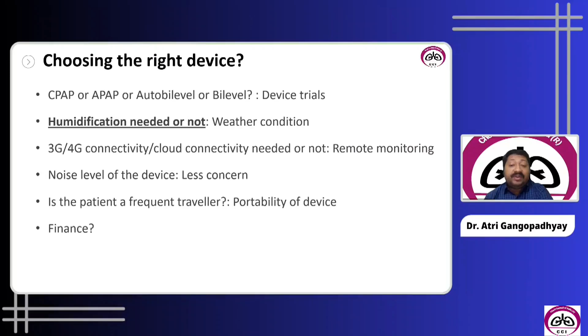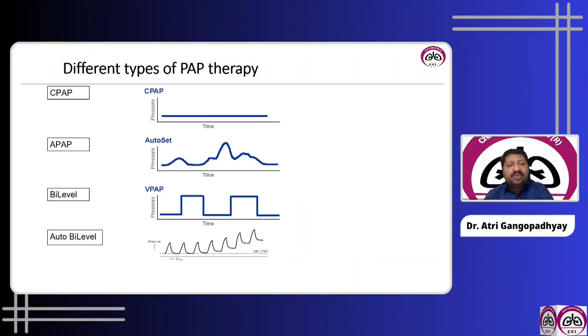Look at these diagrams. CPAP, or continuous positive airway pressure: the pressure of the device does not change over time. APAP, automated positive airway pressure: depending upon the patient's breathing resistance, the pressure can change over time. Bilevel: here there are two pressures, one inspiratory, one expiratory. And auto bilevel: here also there are two pressures, but there is a fluctuation for both the pressures. So ultimately, whatever machine you have in the market boils down to these four things.